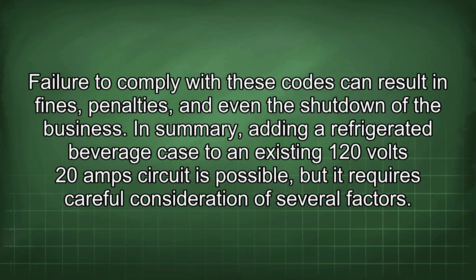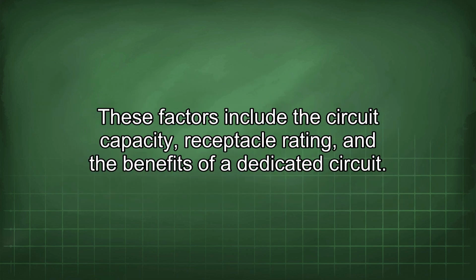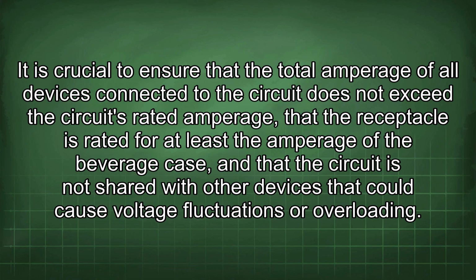In summary, adding a refrigerated beverage case to an existing 120 volts 20 amp circuit is possible, but it requires careful consideration of several factors. These factors include the circuit capacity, receptacle rating, and the benefits of a dedicated circuit. It is crucial to ensure that the total amperage of all devices connected to the circuit does not exceed the circuit's rated amperage, that the receptacle is rated for at least the amperage of the beverage case, and that the circuit is not shared with other devices that could cause voltage fluctuations or overloading.